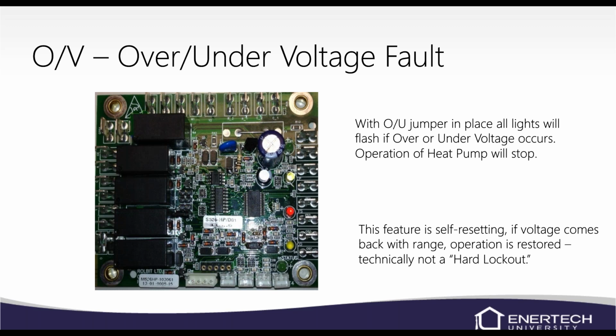If you have a real problem with your under-over voltage light going off, then give us a call at tech support. There's been a few times when we have to not monitor that. It usually happens in a very rural situation where their power is not real stable. And so we may have to not monitor that. If you think that's a possibility, just give us a call at tech support and we'll discuss it, check a few things real quick, and then we'll make a note that we told you to do that. That way, if something were to happen down the line with the board, you're covered on your warranty status.